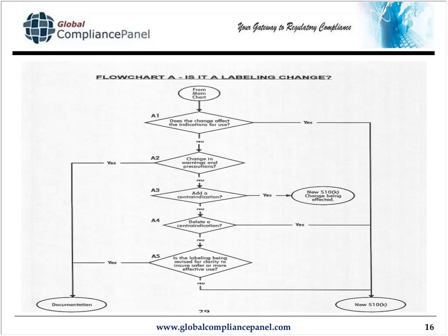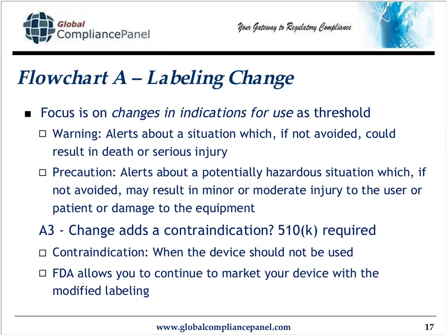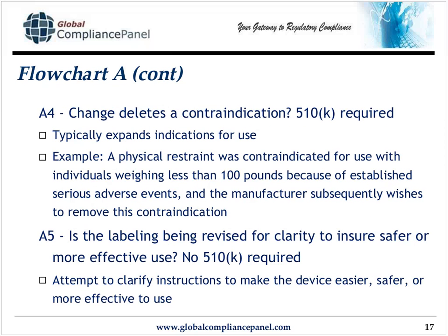A4 says, is my labeling changed? Am I deleting a contraindication? If the answer is yes, I must submit a new 510K, because when you delete a contraindication, as opposed to adding one, you're typically expanding the indications for use. An example is there's a physical restraint. Previously, it was contraindicated for use with individuals who weighed less than 100 pounds. But now I want to remove this contraindication.